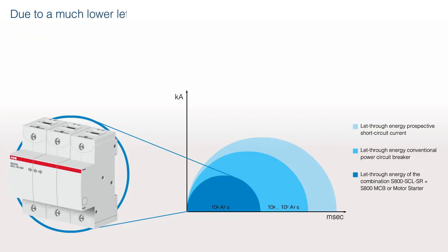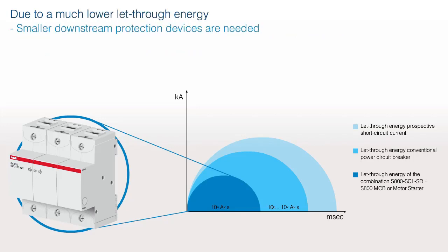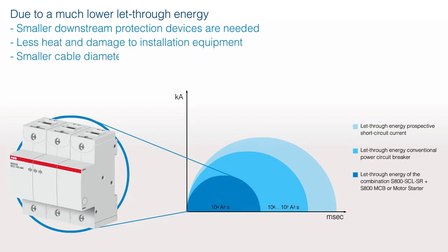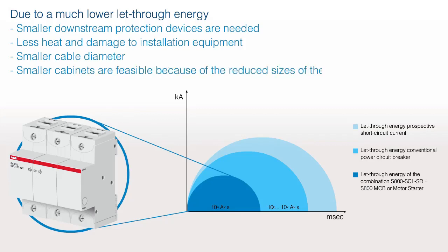Due to a much lower let-through energy, smaller downstream protection devices are needed. Less heat and damage to installation equipment. Smaller cable diameter. Smaller cabinets are feasible because of the reduced sizes of the device.